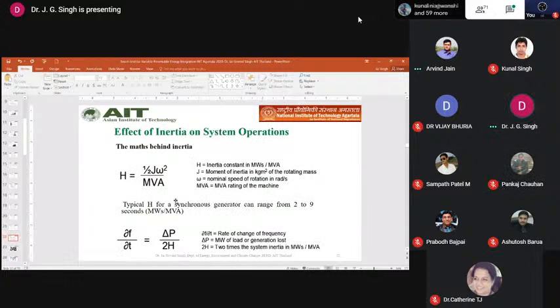So, in terms of inertia, in per unit terms, the rate of change of frequency is related to the change in P, divide by H. P is all load and generation, any changes. If you have a high H value, the rate of change of frequency will be low. The rating itself isn't the big deal—the main thing is J, the moment of inertia, in kilogram meter square.